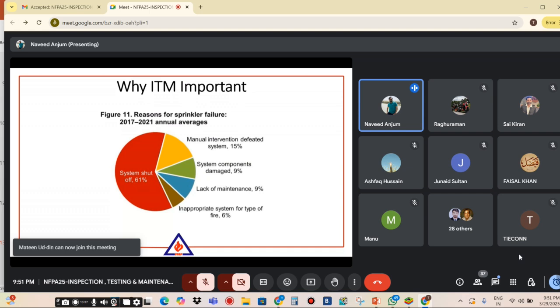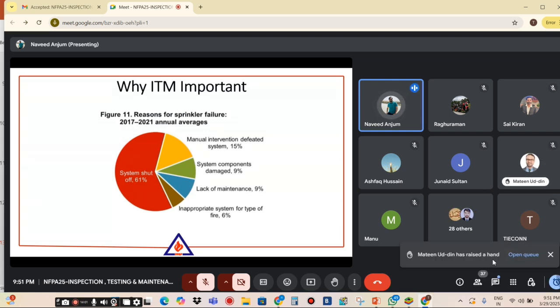And the second main reason is manual intervention defeating the system. Someone manually caused issues and it is not working properly, or some component is damaged, and 9% is basically lack of maintenance, where the system is not maintained and because of this the sprinkler does not work properly. And the last is an inappropriate system for the type of fire, meaning they have not designed the system as per requirement. Like if we have not designed our sprinkler system as per our hazard, then in case of fire, the sprinkler will not work properly. If someone wants to ask any questions, we will give you time at the end of the session, and you can ask any question at the end of our presentation.